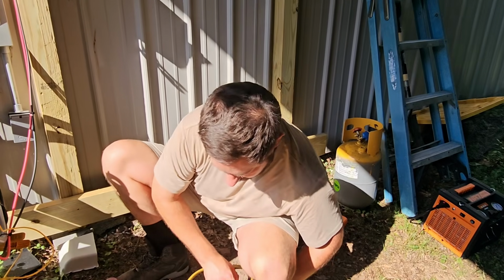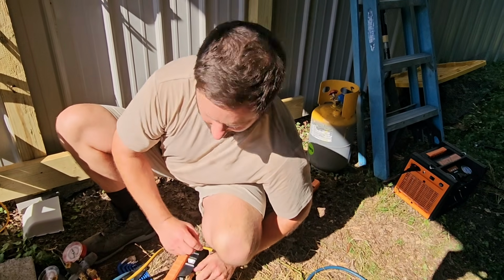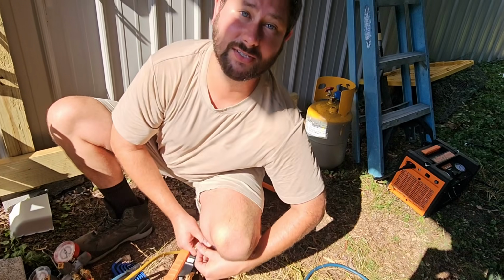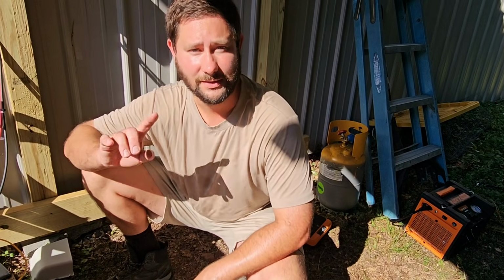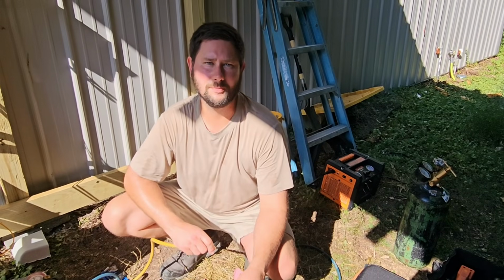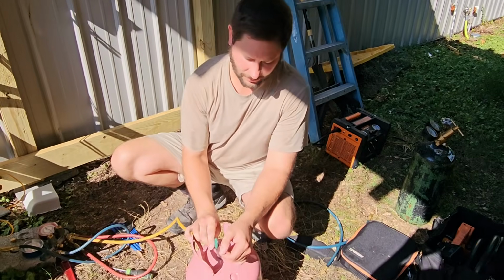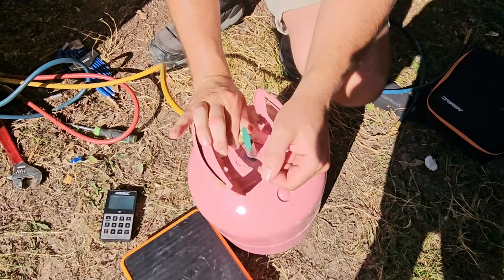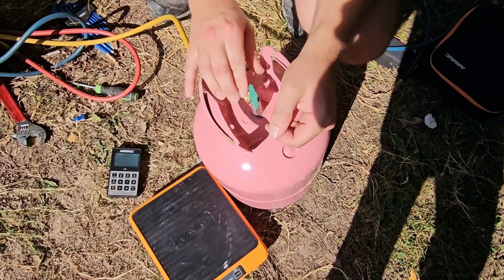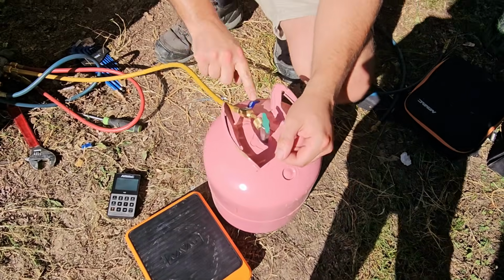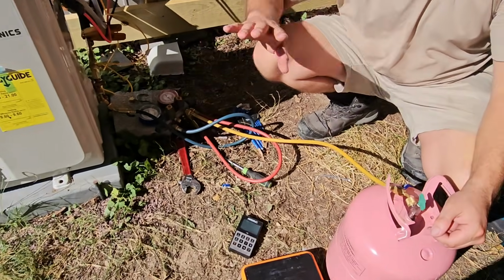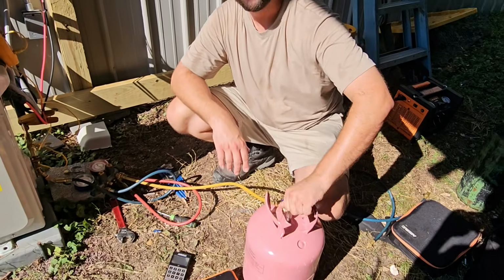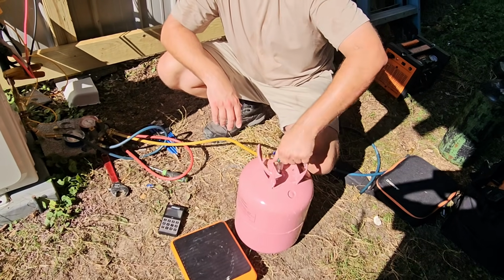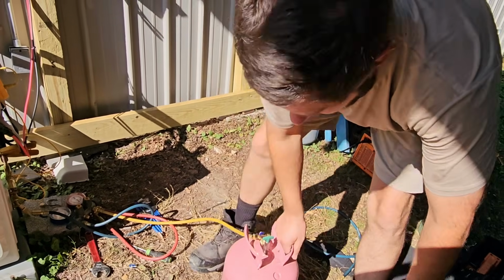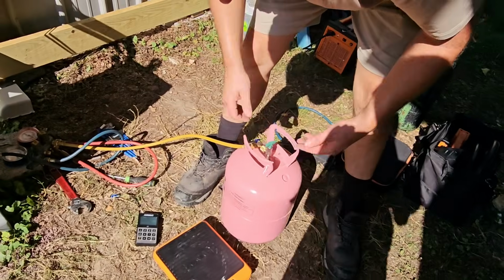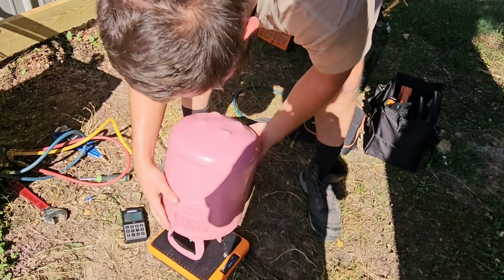Now that we have pulled a good vacuum and used our nitrogen, we're going to charge up the system. And I'm going to show you how to charge this mini split. We're going to connect our yellow hose to our tank, leave this valve closed, leave our gauges closed, and open up the valve on top of the cylinder. We're going to charge not as a vapor, not this way. We're going to charge as a liquid this way.